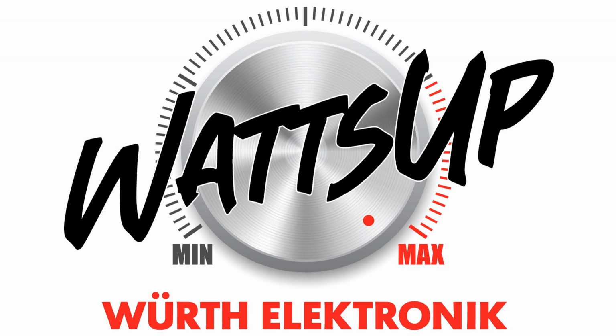Again, very often to see this kind of very wrong connection, that you come with a cable, you put the filter and you turn back again, and you have your capacitive and inductive coupling into the metal box enclosure. Especially industrial electrical guys, they just take the easy way, just connect to the wall in the very correct way, in the shortest way, but then they route the cable again close by the entrance, and again it's a big problem. So try to do in the construction that you're not crossing or not coming close to this area where you have the filtering effectivity, because else it won't work so good.